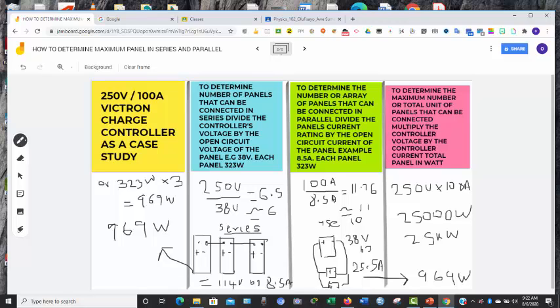So I will be dividing the current of my panel by the open circuit current of the panel. The open circuit current of the panel is 8.5, while the current for the charge controller is 100 amps. So I am able to get 11.76, and rounding it down, it will be about 11. But ideally, when doing panels in parallel, it is better to follow an even number, so one can use 10 panels instead of 11. But we can still use 11 panels; that will still be very okay for this design.